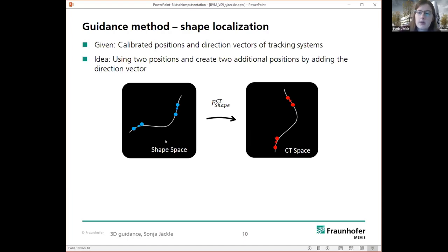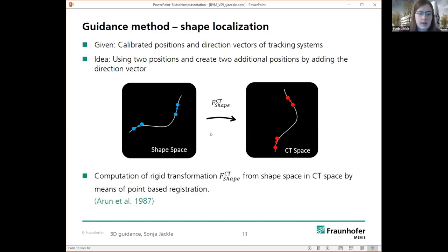And in the same way, we have this also in the shape space, the two corresponding positions from the EM sensors, and also two additional points with the direction vectors. And then, in the end, we are using a point-based registration to compute a rigid transformation to transform the shape to the EM tracking coordinates in the CT space.